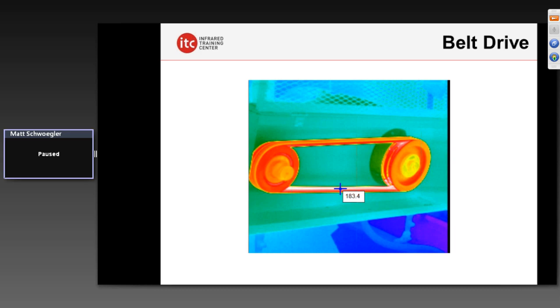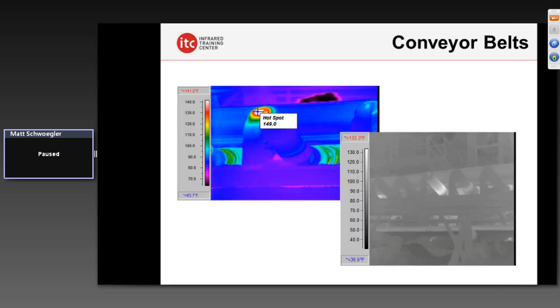Belt drives, belts, and sheaves should run at or near ambient temperature. If they're not, it could indicate a loose belt, an over-tensioned belt, or a misalignment-related issue. Infrared won't exactly pinpoint what's happening, but it gives you a data point that you want to look at more closely — in this case, this belt is running far too warm and is something we want to diagnose and fix.